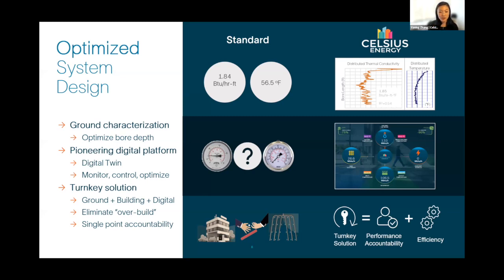While we're installing the loops, we can characterize the ground to see the actual heat transfer capability at various stages of the ground, instead of a one-point capture, which is the standard in today's industry. Because we know what the different levels of the ground allow for heat transfer capacity at various stages, we can design the solution to optimize the system.